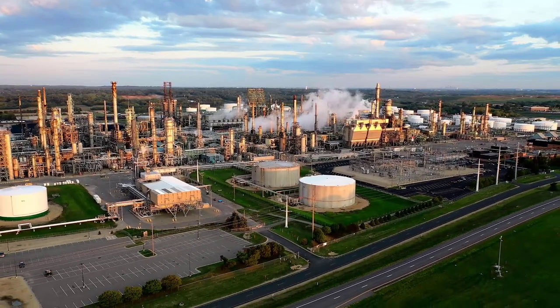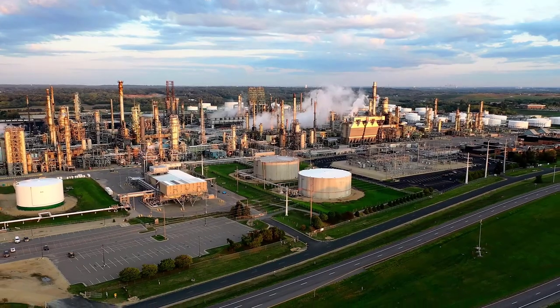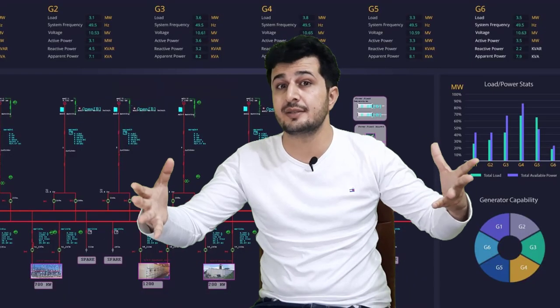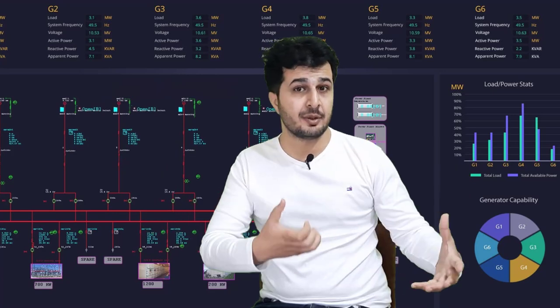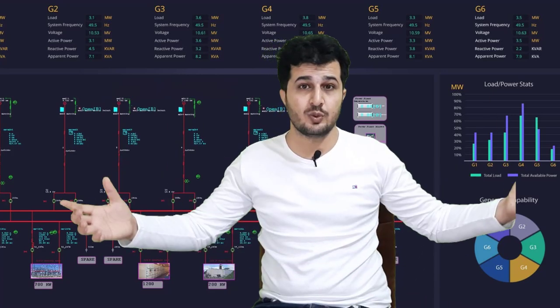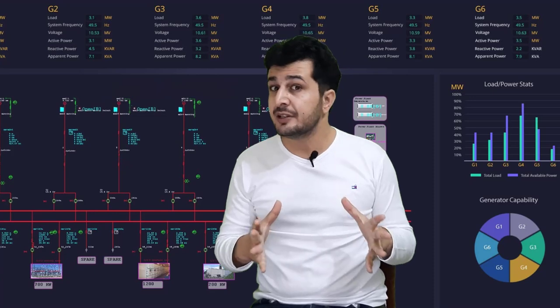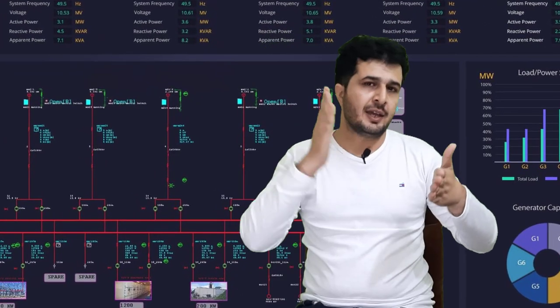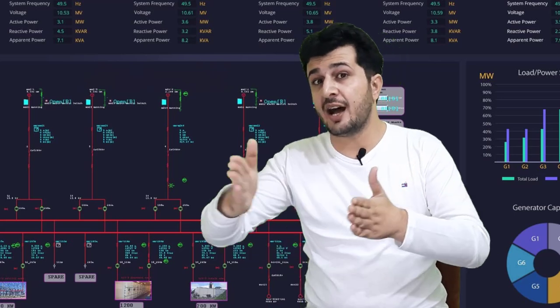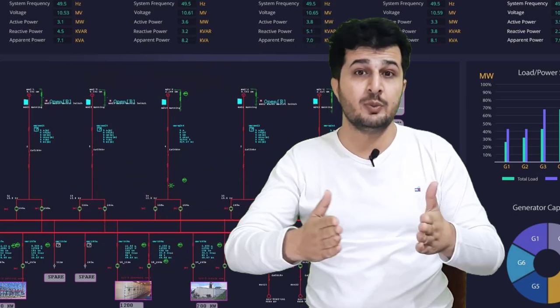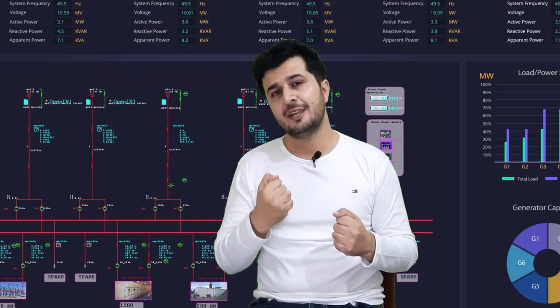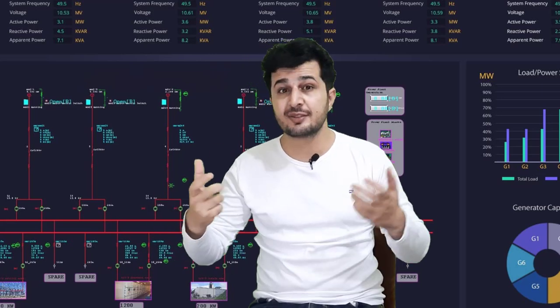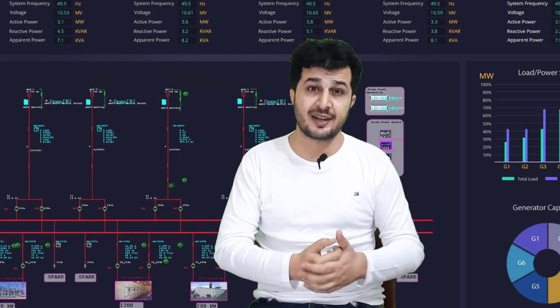Due to the wide range of networking features of DCS, it is easy to determine faults and monitor plant production rate. Industrial networking has become really important, and because of this, PLCs have become a section of a DCS. This is a very important concept: a PLC can be part of a DCS system, and you can get data from a PLC on a DCS network. Redundancy is an important feature of DCS — each area has different controllers, not just one.